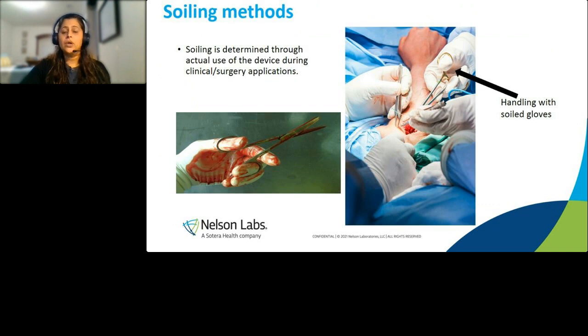This gives you an example of what I'm talking about with simulated use soiling. This is how it is actually being used, and this is the amount of test soil we're using. This is my hand with gloves that are contaminated with test soil, and I'm holding the scissors. I've actually soiled it more than what you see here to challenge the processing, just in case. If the scissors get very soiled, then how can we clean it? So we have to think about worst case scenarios when we're doing these methods as well. We will soil them to way worse case than what the procedure would be contaminated with, as you can see here.